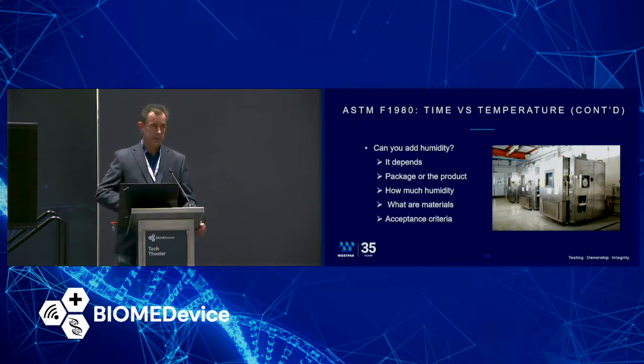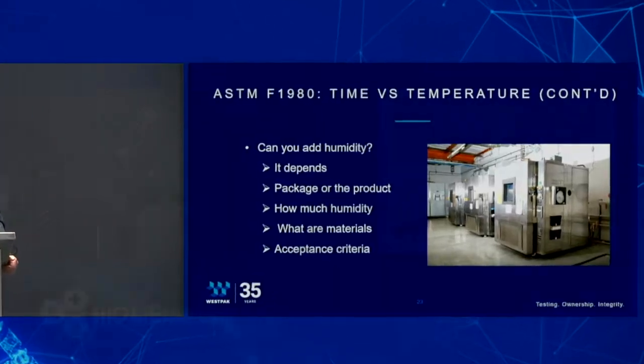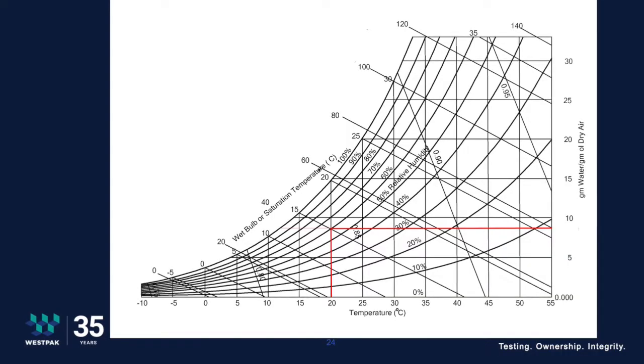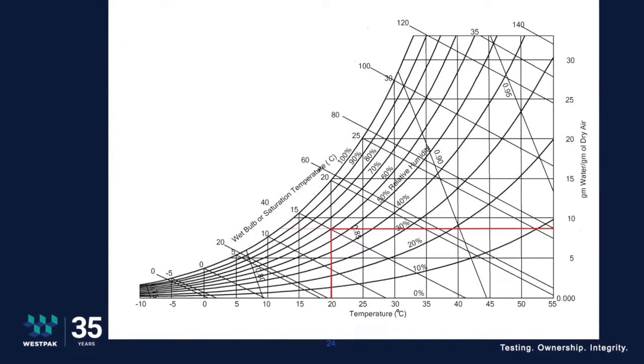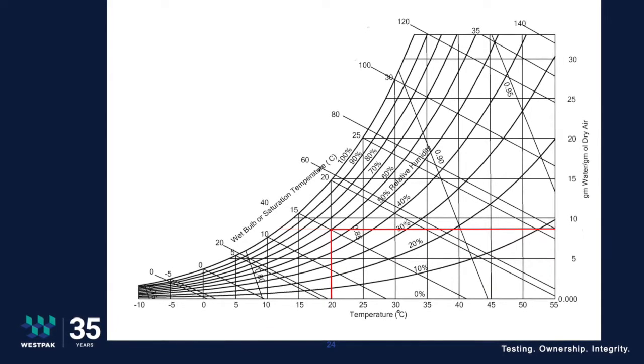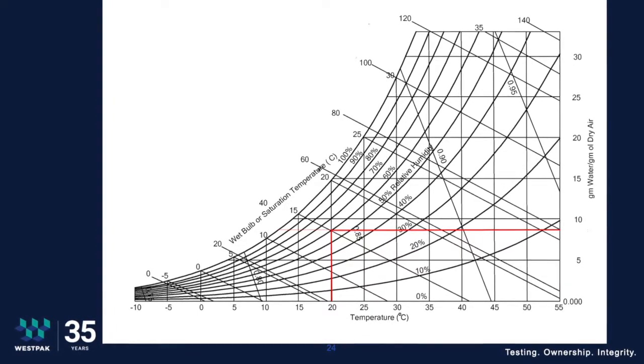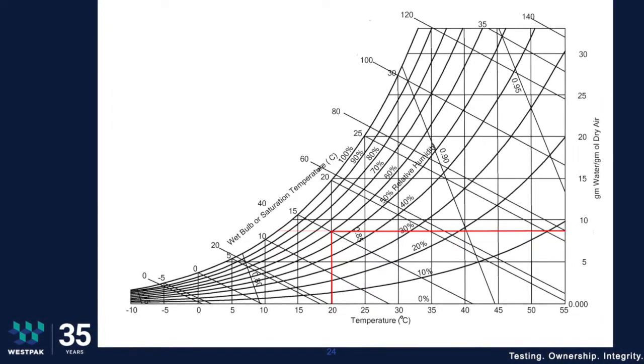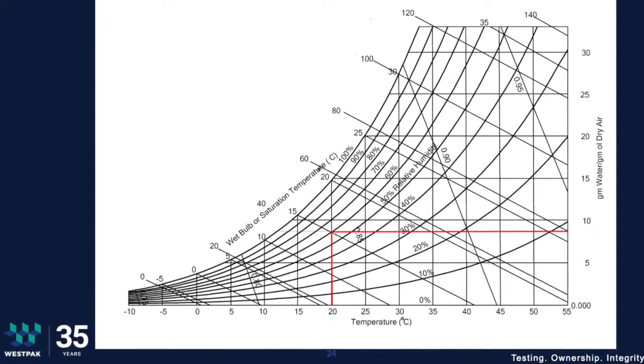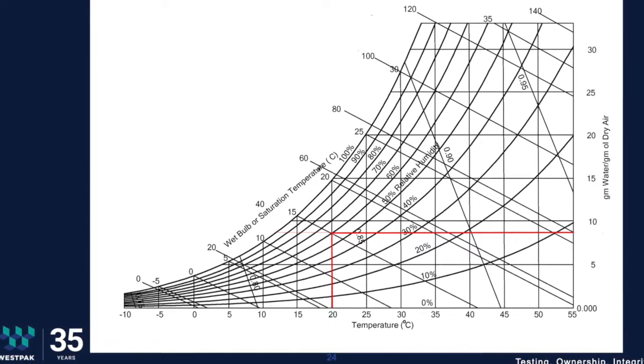If we do want to add humidity into the equation, how much humidity? And what should our acceptance criteria be? Let's take a look at what humidity might look like. This is a basic psychrometric chart. It illustrates the dry bulb temperature on the x-axis and the wet bulb temperature, which is used to measure relative humidity. On the far right y-axis, we have a ratio of grams of water per gram of dry air. In the middle, we have lines sweeping up from 10, 20, 30, 40, 50, all the way to 100% relative humidity.